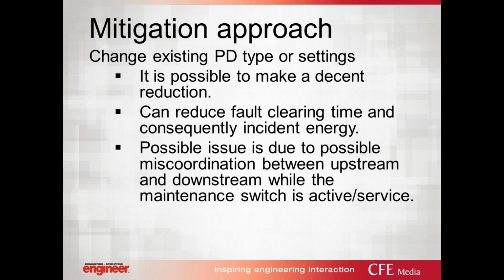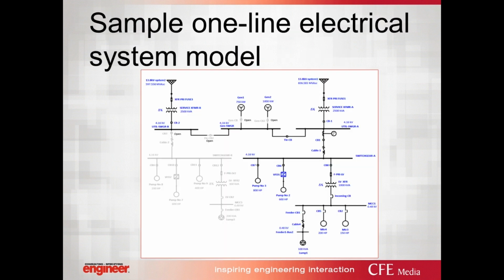Okay, mitigation approach, and continuing on that: changing existing protective device type and settings. It is possible to make a decent reduction, can reduce fault clearing time, and of course, reduce the incident energy at the same time. A possible issue with this one may be miscoordination in some cases, where we have to either sacrifice the coordination or reducing the incident energy, which I never recommend, and no one would recommend sacrificing any coordination to reduce incident energy.